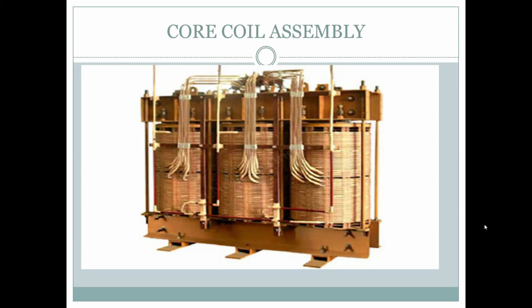You will not believe it: when this core is made ready in the oven, we get buckets full of water. We cannot imagine that so much moisture is absorbed by this. Until it is dried, it cannot be used. So it goes through the cycle of pressure and heat. This cycle is defined. I'm not going to touch on that. For every insulation grade and every voltage class, a cycle is defined. You have to continuously run that cycle. Next.